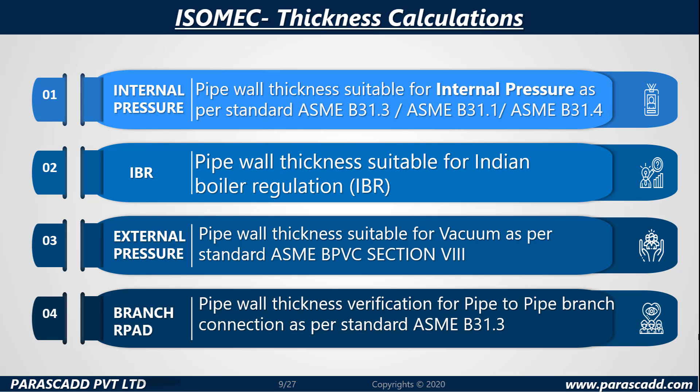Isomec thickness calculations cover four areas. First, internal pressure: pipe wall thickness must be suitable for internal pressure as per ASME B31.3, B31.1, and B31.4. Second, IBR: pipe wall thickness must be suitable for Indian Boiler Regulation. Third, external pressure: pipe wall thickness must be suitable for vacuum as per ASME BPVC Section 8. And lastly, the branch repad: pipe wall thickness verification of pipe-to-pipe branch connection as per ASME B31.3.